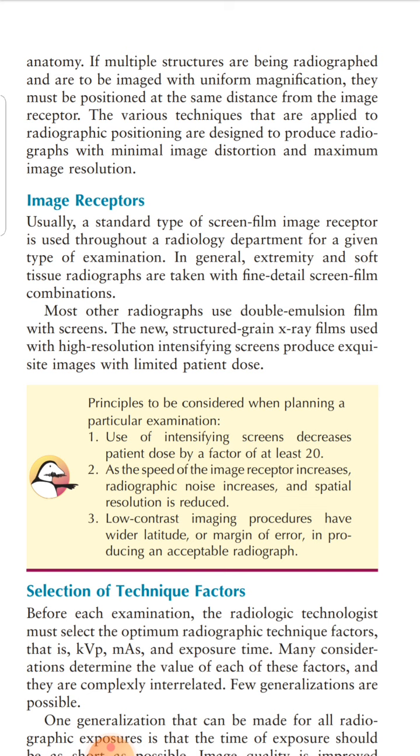The low contrast imaging procedures have wider latitude or margin of error in producing an acceptable radiograph. Latitude means the range of exposures for which your radiographic emulsion can produce acceptable contrast. And when I am talking about the low contrast imaging procedure, that means we are talking about those procedures in which we are going to cover those structures with uniform contrast.